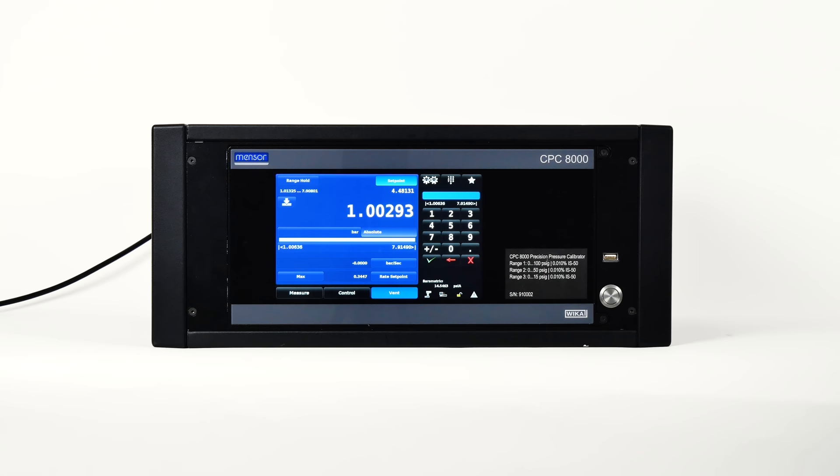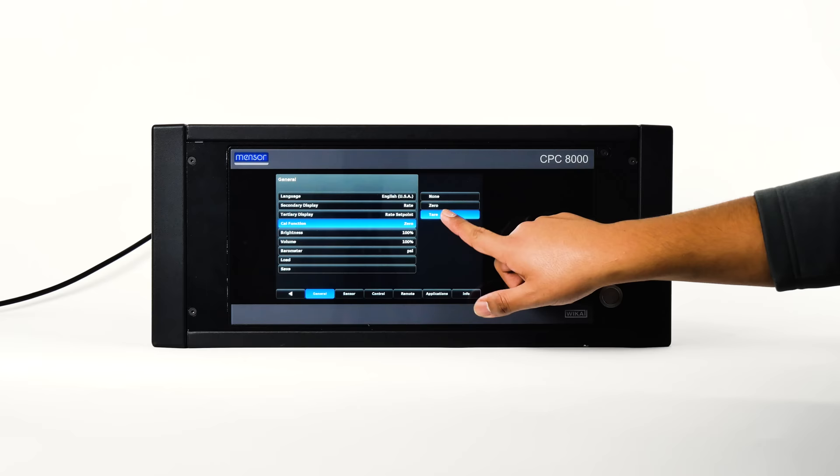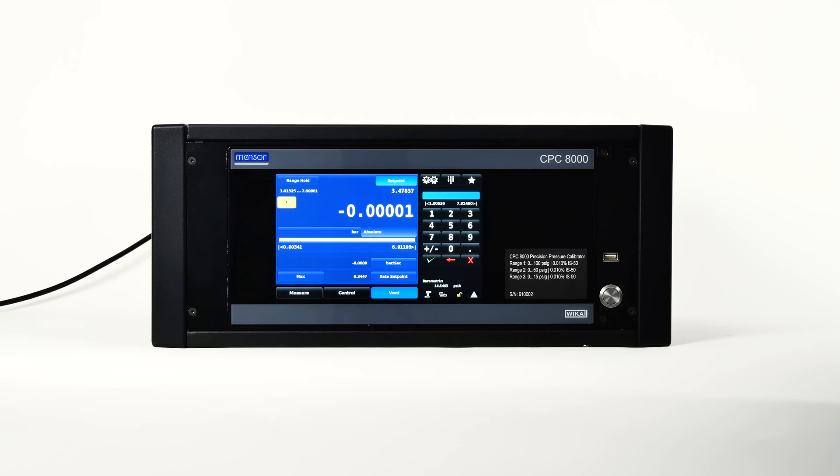If the tare calibration function has been selected in the display settings app, the tare button will appear in the home screen. When the tare button is pressed, the instrument will subtract the current pressure reading so that the indicator will display zero. Subsequent deviations in pressure will be relative to the tare pressure. The button will be yellow to indicate the pressure reading is affecting the offset. Press the tare button again to deactivate it.